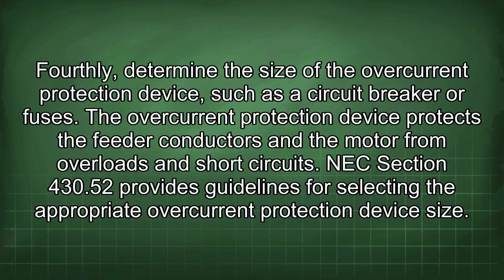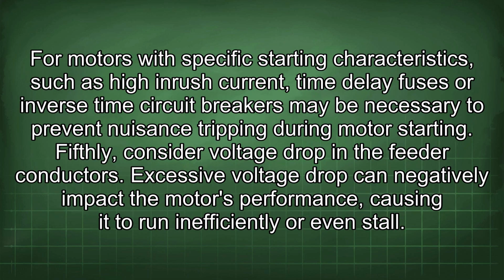Fourthly, determine the size of the overcurrent protection device, such as a circuit breaker or fuses. The overcurrent protection device protects the feeder conductors and the motor from overloads and short circuits. NEC section 430.52 provides guidelines for selecting the appropriate overcurrent protection device size. For motors with specific starting characteristics, such as high inrush current, time delay fuses or inverse time circuit breakers may be necessary to prevent nuisance tripping during motor starting.